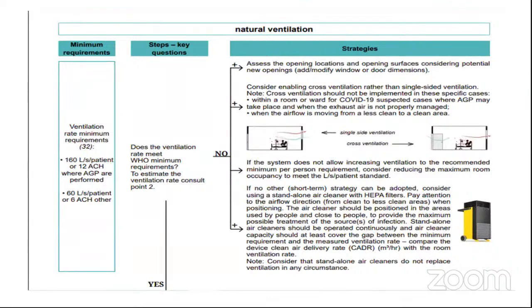So the first step is we need to ask whether the ventilation rate meets the WHO minimum requirements. Now, what are the WHO minimum requirements? The WHO minimum requirements are at least 12 air changes per hour, especially where aerosol generating procedures are being performed, or 160 liters per second per patient ventilation rates. If this is not being fulfilled, then we need to assess the opening locations.